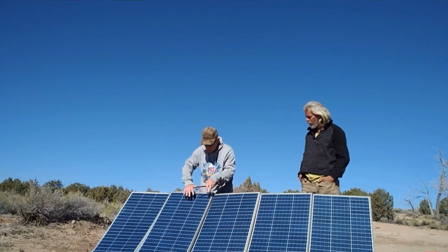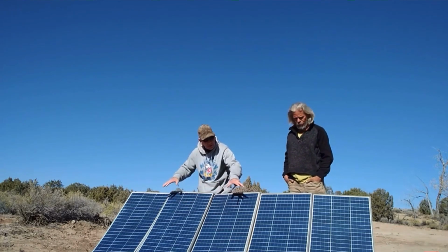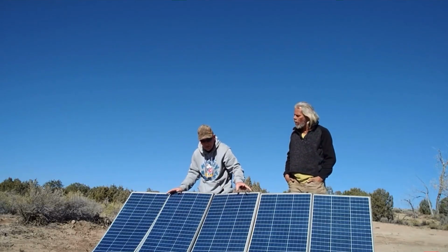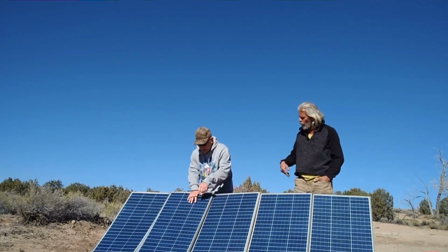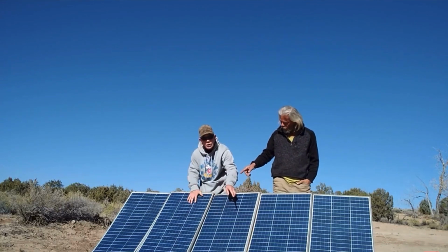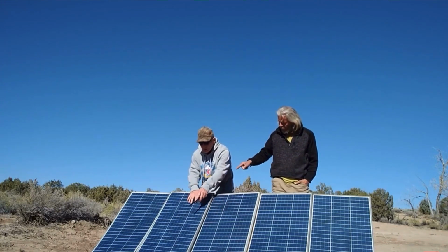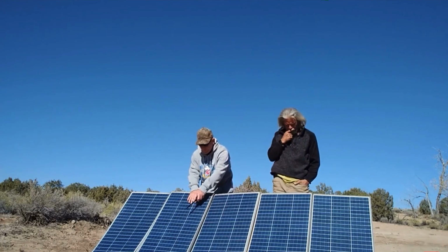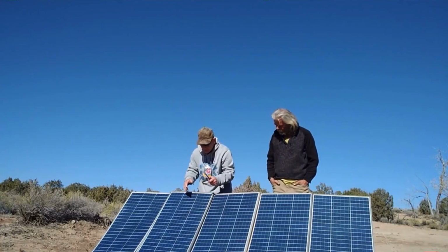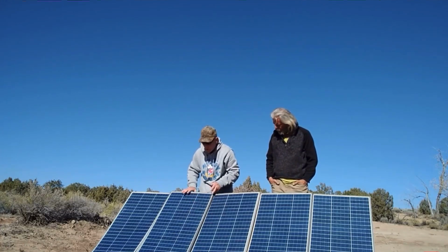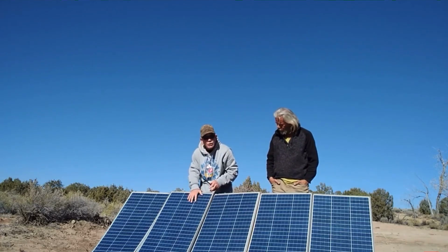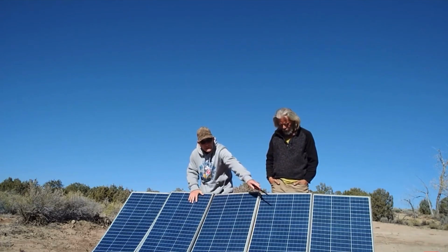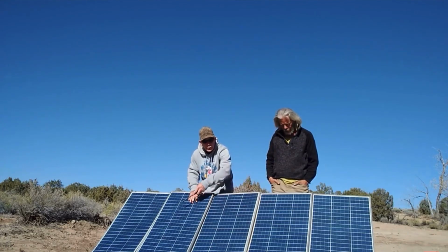Yeah, because it will block off the cells, and especially when they're hooked up in series, it will actually affect all of them and bring them all down to the production of the one panel, because each one relies on the other. These are probably 75 watt panels, so if one panel is only producing 30 watts because it's got blockage on it, all the other panels, even though they aren't shaded, are only going to produce 30 watts.